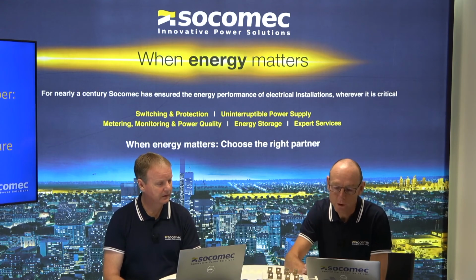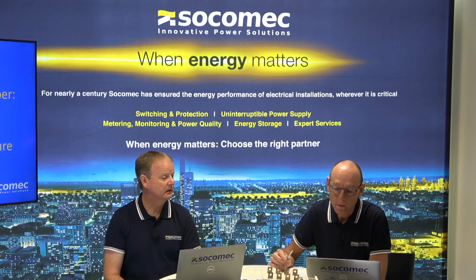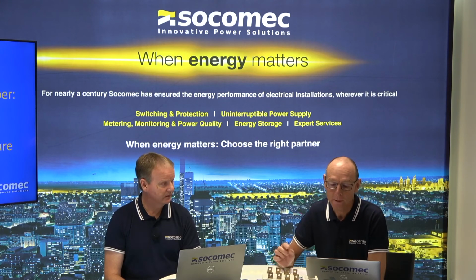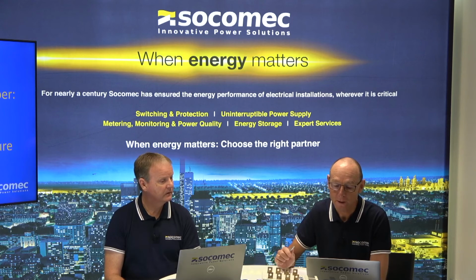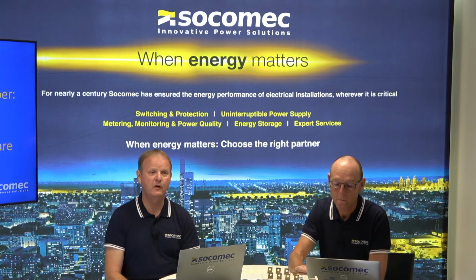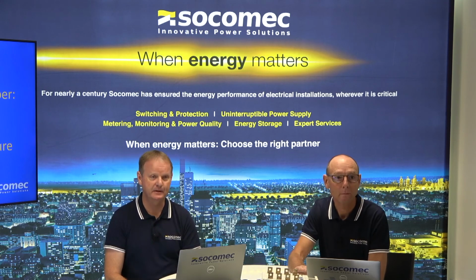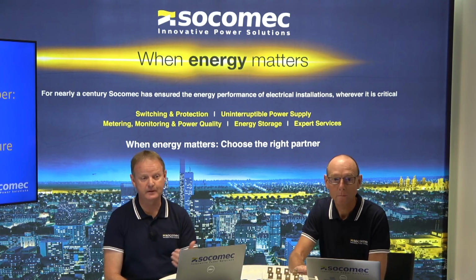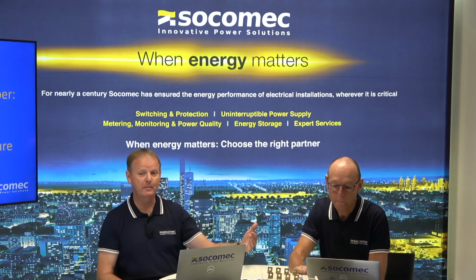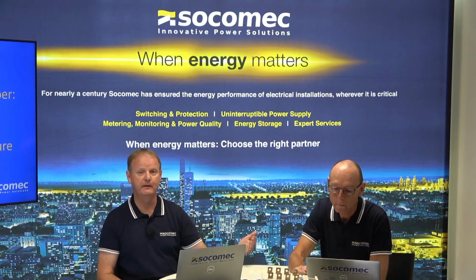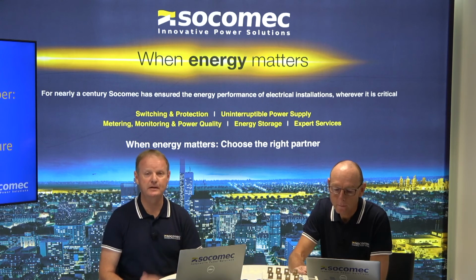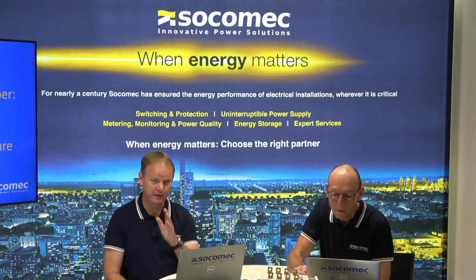A question here from James. If I am an FM company looking after an existing building, do I need to reinstall new transfer switches in line with the new 2020 standard, or is the current installation fine? From what we understand, the current installation is fine. However, once you make a modification to that installation, so you need to change or upgrade something, then you must conform. So you don't have the risk of having to redo everything when you take over a building. But as soon as you change something within that low voltage schematic or that installation, then you must make sure it conforms to the new standard. It's a good question though, James, very good.